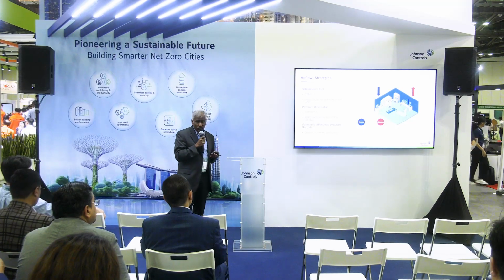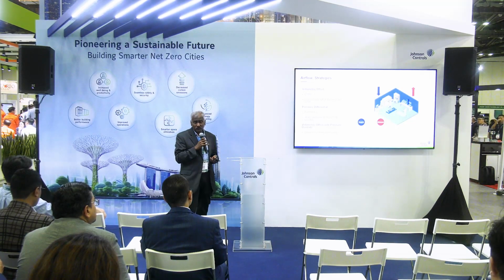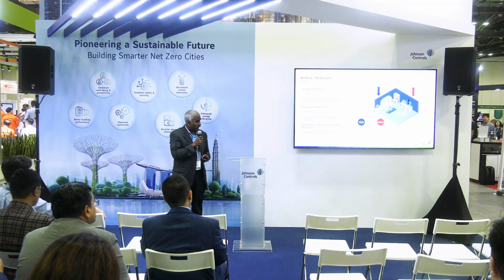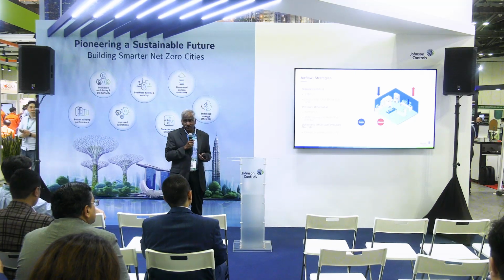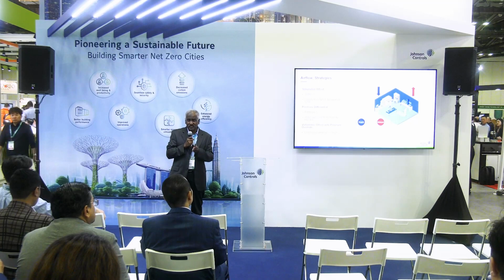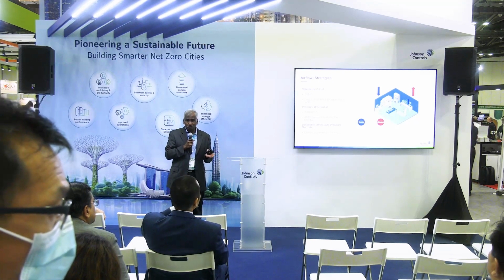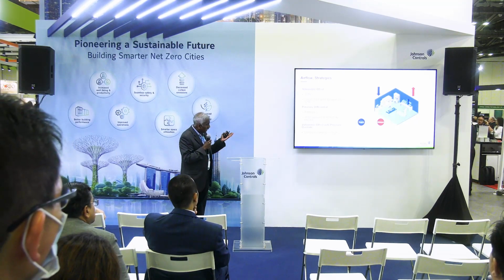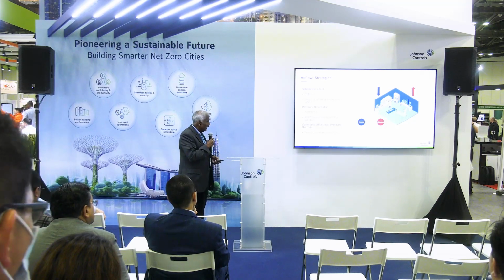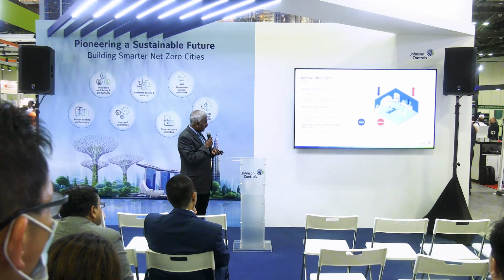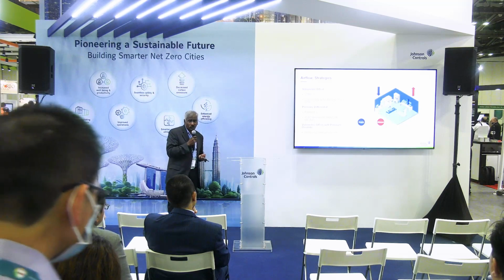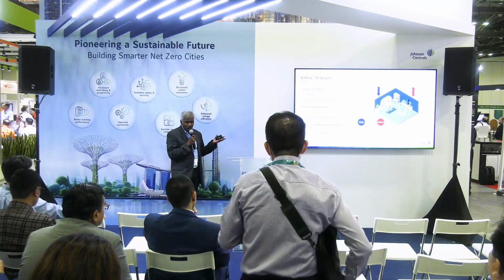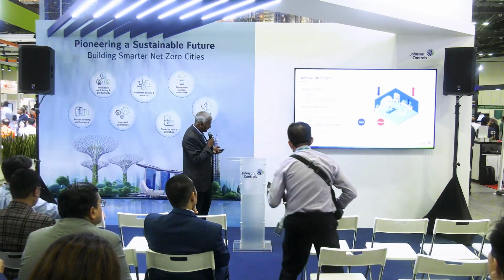Then you have a pressure differential. That's very common in a hospital environment for critical environments, right? So typically you have 0.01 inch water column. That's the difference that you need to maintain, to be positive or negative pressure, or 2.5 pascals, right? And the other one is volumetric offset with pressure and override. This is typically used for a fume hood application, hardly used in the normal hospital environment.